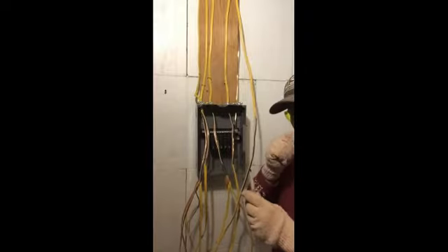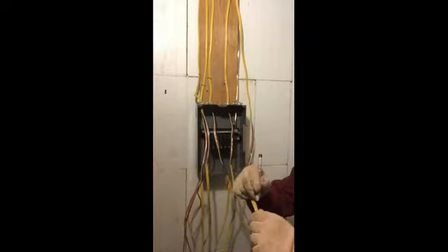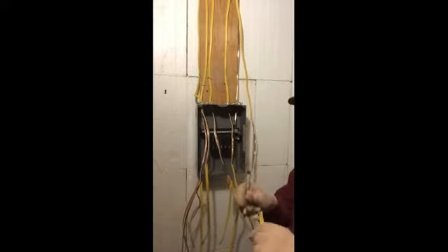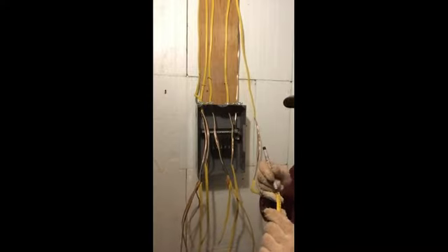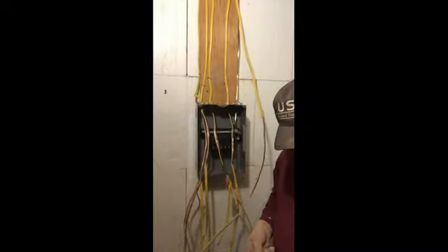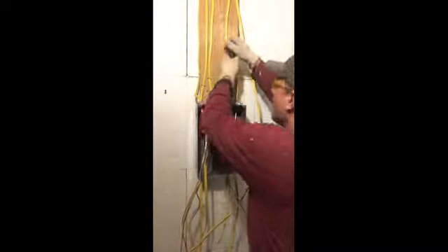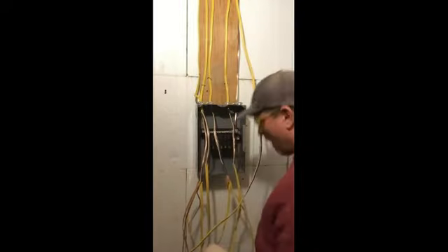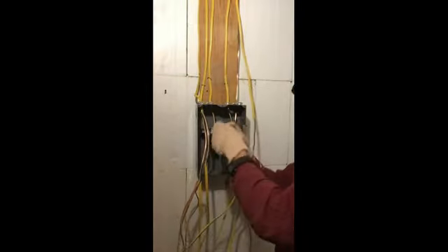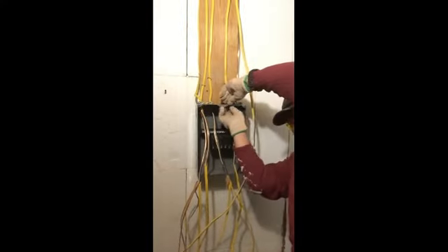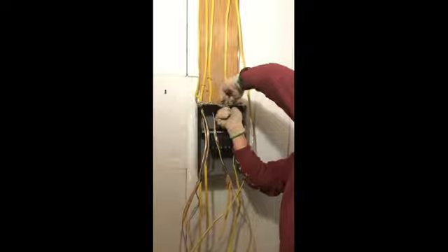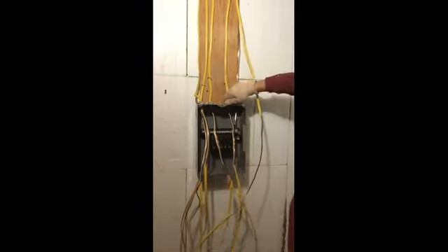Your bare wire will go to the bus bar in your panel box, which is actually your grounding wire, which takes the brunt of an electrical shock should there be a short in an appliance. Your white wire is the neutral wire. It goes to the opposite bar in the panel box. However, your bare bus bar and your neutral bus bar will actually go to the same grounding rod outside, but it's imperative that they go to separate bus bars in your panel box. Make sure you understand that. And your black wire will be wired to your circuit breaker, which you will install as you go down the list and snap them in one at a time. Repeat this process for all the circuits in your house.